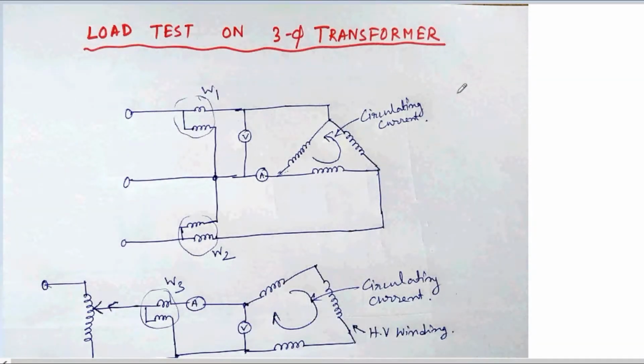Here, load test on three-phase transformer. Load test means back-to-back test or Sumpner test on a three-phase transformer, and we know that this test is required to determine the temperature rise of the transformer, and it is also useful to determine the efficiency.